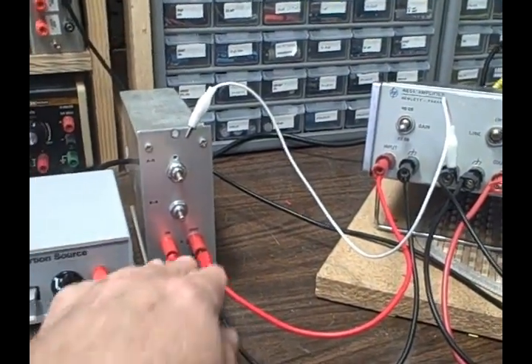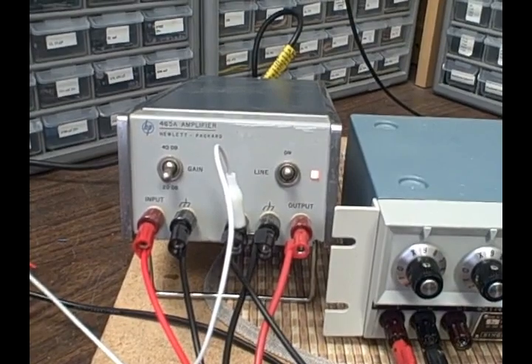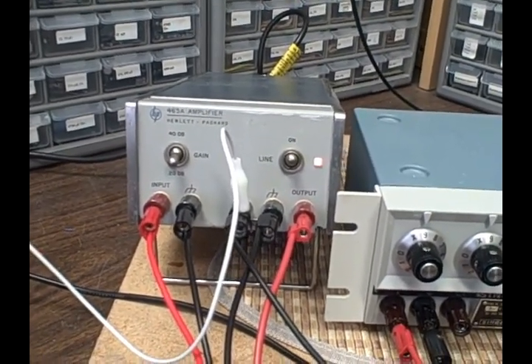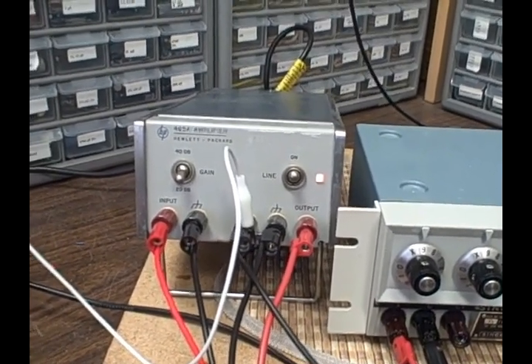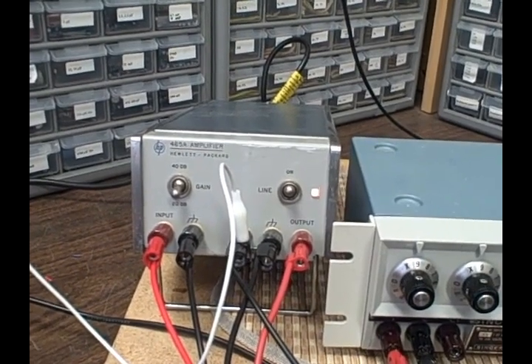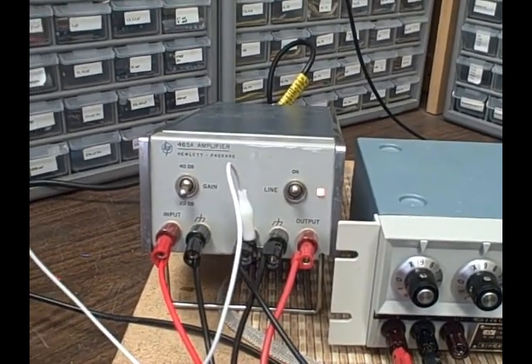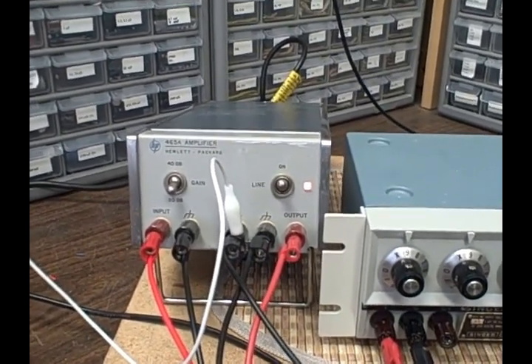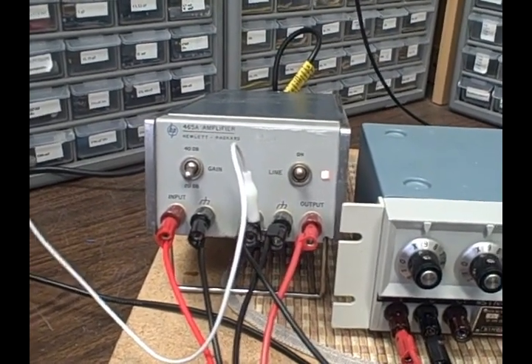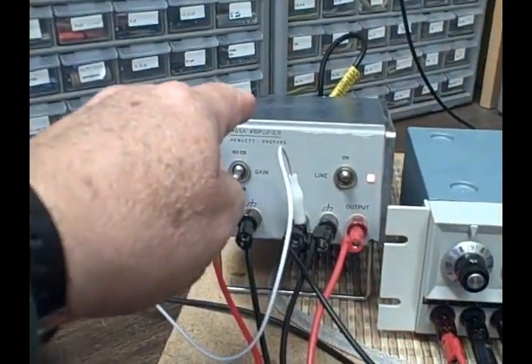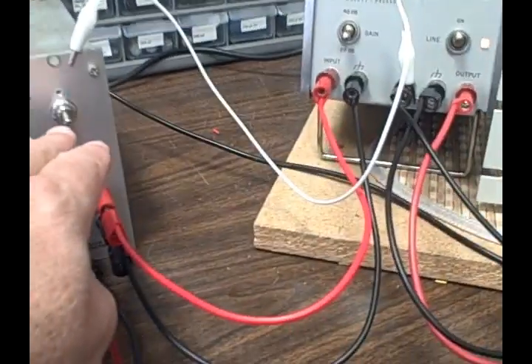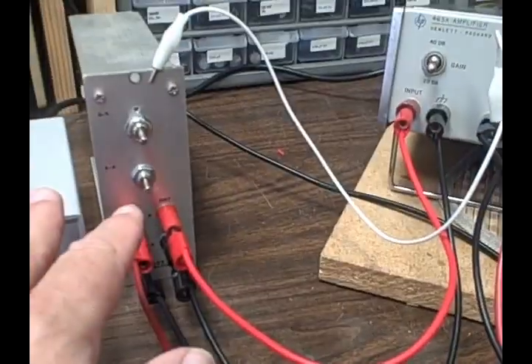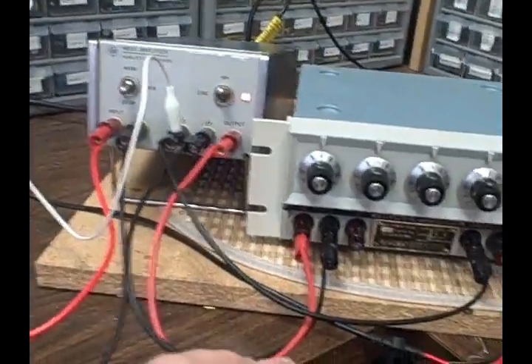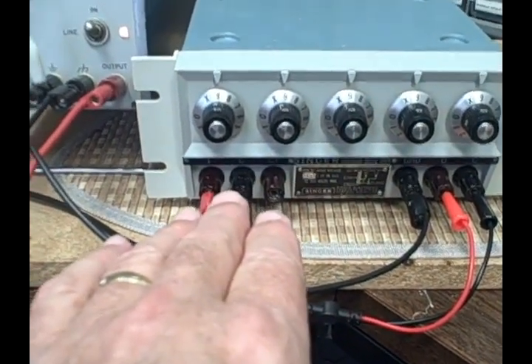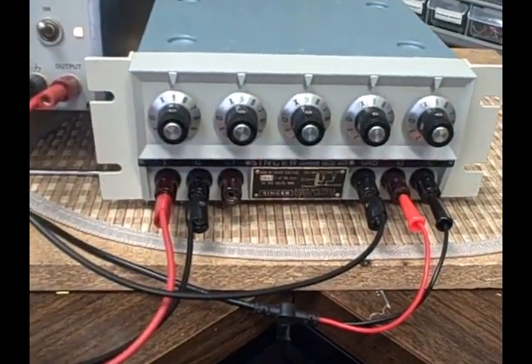The signal that comes out of that goes into my amplifier here, which in this case is a Hewlett Packard 465A, which has a frequency response, I think 2 dB from 5 hertz to about a megahertz, and it's very flat from like 100 hertz up to, I don't know, 10 kilohertz, something like that. I don't remember the exact spec, but I'm thinking it was within half a dB, maybe better. Anyway, I'm amplifying up that signal that comes from my low distortion source, which has been voltage adjusted here. I adjust it so that the output of that amplifier provides the 10 volts I need to go into this Gertsch ratio transformer.